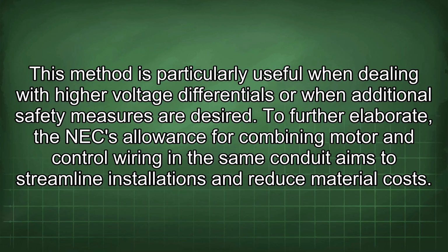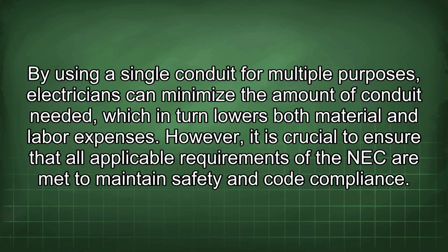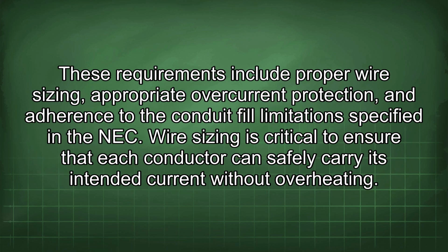To further elaborate, the NEC allowance for combining motor and control wiring in the same conduit aims to streamline installations and reduce material costs. By using a single conduit for multiple purposes, electricians can minimize the amount of conduit needed, which in turn lowers both material and labor expenses. However, it is crucial to ensure that all applicable requirements of the NEC are met to maintain safety and code compliance. These requirements include proper wire sizing, appropriate overcurrent protection, and adherence to the conduit fill limitations specified in the NEC.